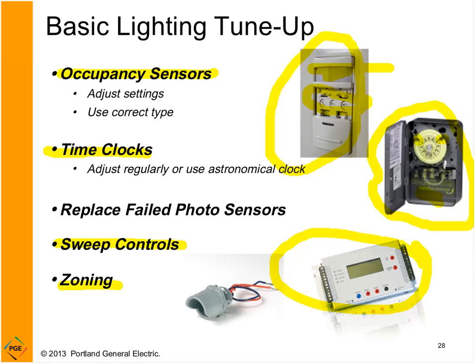Zoning is another key thing. You want to make sure that your light switches are controlling lights in the area that they're in. I've been in some facilities that have gone through a retrofit, for example, and now a light switch on the east side of the building controls lights in the warehouse on the west side. I mean, that's an extreme case, but if you don't have a light switch located properly, the occupants aren't going to take the opportunity to turn off the lights when they should.